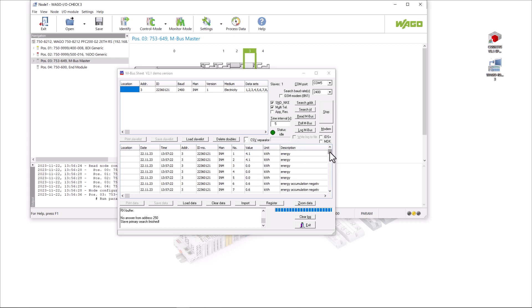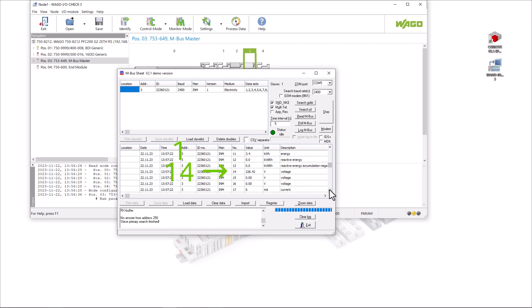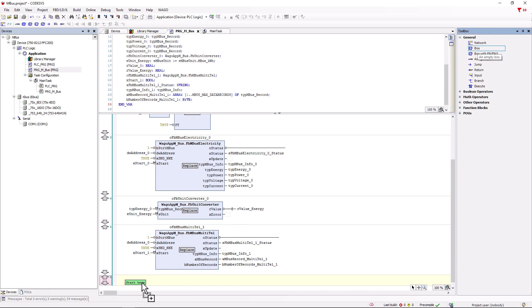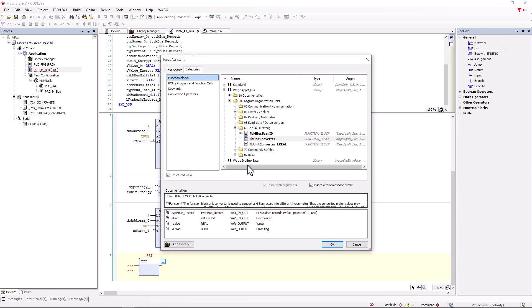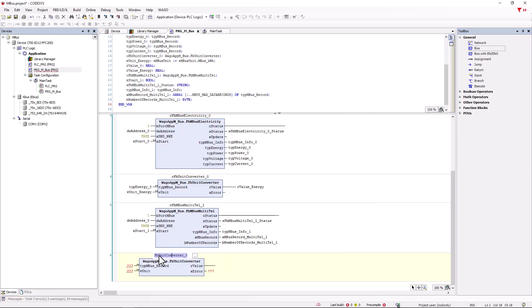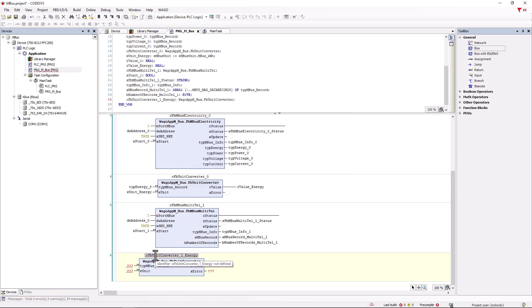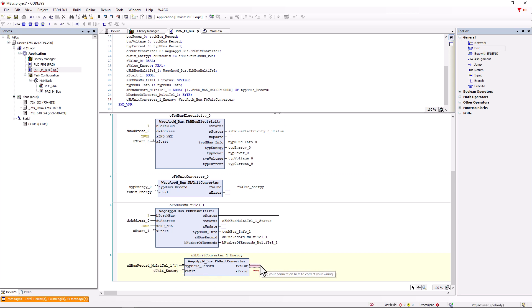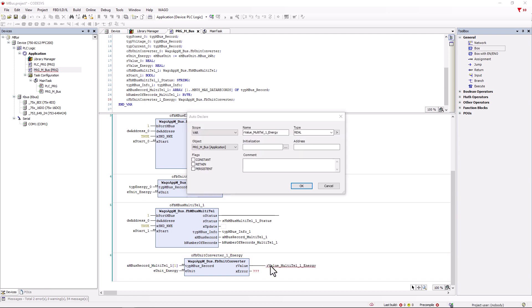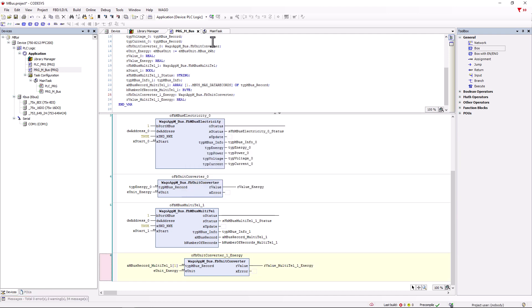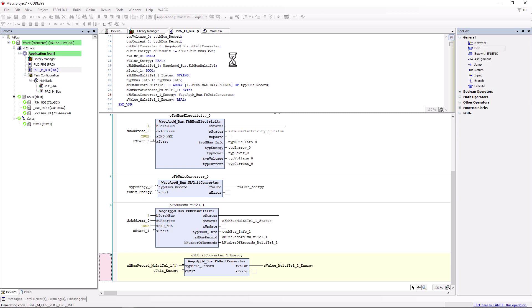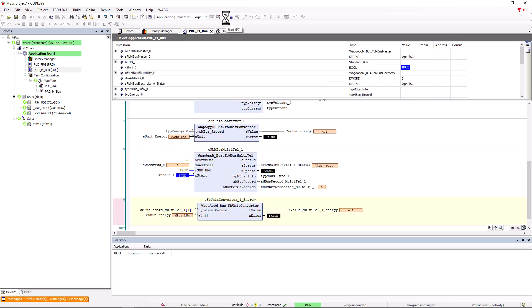To use multiple values in the CodeSys, we note the corresponding array numbers. For example, total energy number 1, voltage on phase 1 number 14 and current of phase 1 number 17. Back in CodeSys, we create a new network in which we call up the function block FB_unit_converter. This should convert the total energy, so we enter the array from the Multi-Tel module at the record input and simply enter the previously noted array position in square brackets. We have already created the variable for the energy unit and assign it to the E-Unit input. Now we only need one variable for the output value.